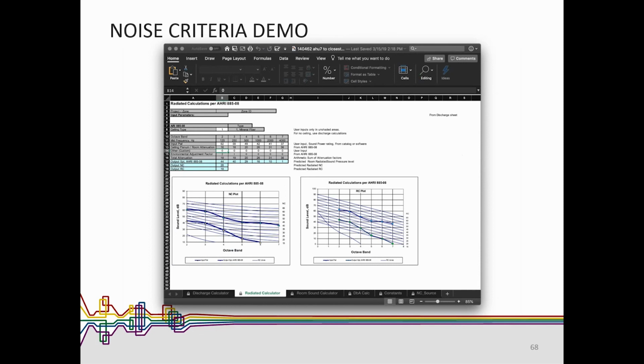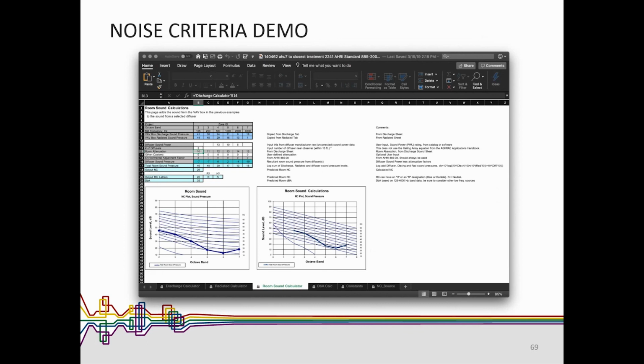Then we go to the next tab, which has us looking at the room attenuation itself. The sound has gotten to the room on the first spreadsheet tab. On the second tab, we look at the room criteria and see what the room is doing to it, how much attenuation we're getting. Then the next spreadsheet has how much sound is coming from the diffuser and the VAV box, and these are getting added in.